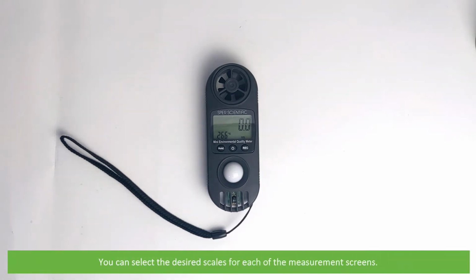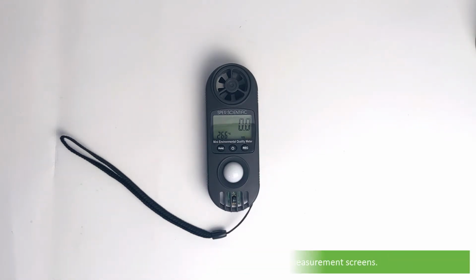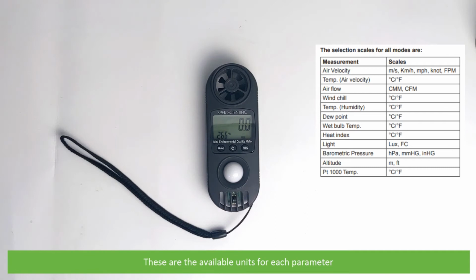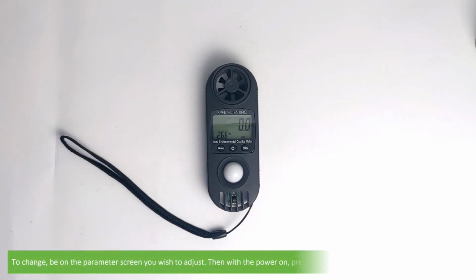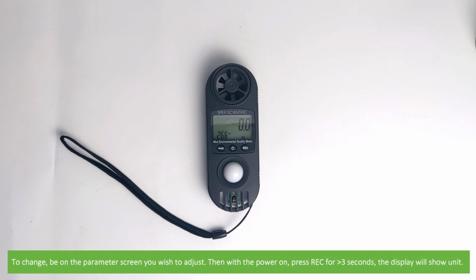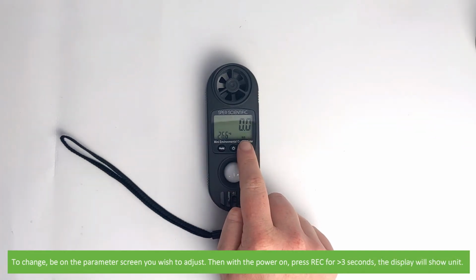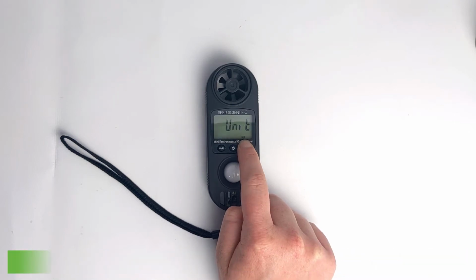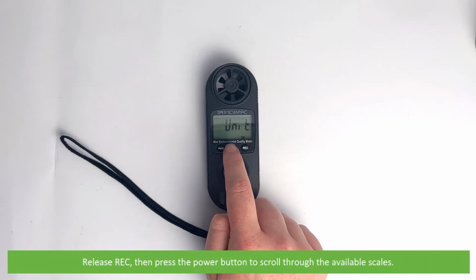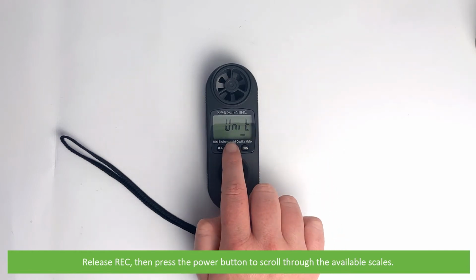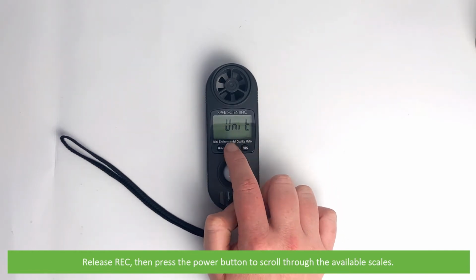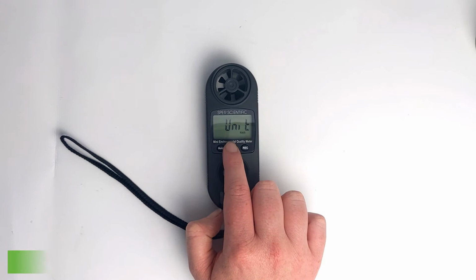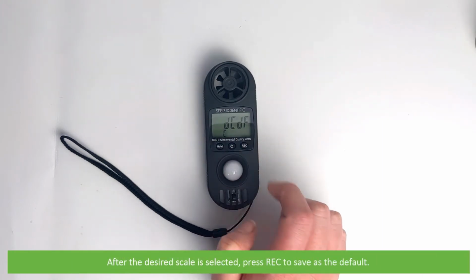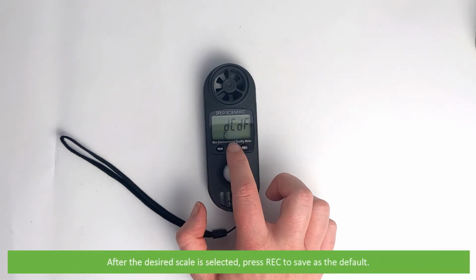You can select the desired scales for each of the measurement screens. These are the available units for each parameter. To change, be on the parameter screen you wish to adjust, then with the power on, press REC for more than 3 seconds. The display will show unit. Release REC, then press the power button to scroll through the available scales. After the desired scale is selected, press REC to save as a default.